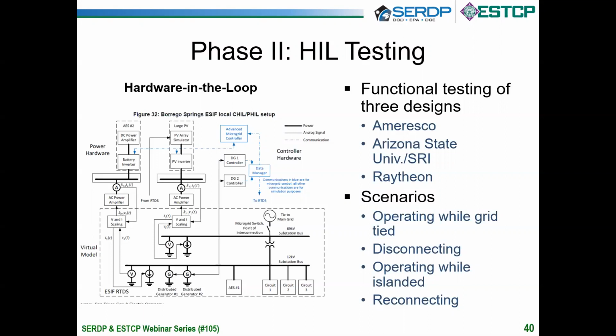So for those of you who aren't familiar with hardware-in-the-loop testing, on this diagram is a one-line diagram of a previous hardware-in-the-loop microgrid test done up at the National Renewable Energy Lab Energy System Integration Facility of the Borrego Springs microgrid. This was a microgrid done by the utility, supported by the California Energy Commission. And the design for the ESTCP hardware loop will look different, but this illustrates the type of questions and the type of setup you can do in a hardware-in-the-loop, where you can put actual hardware: inverters for the PV, inverters for the battery itself, the microgrid controller.